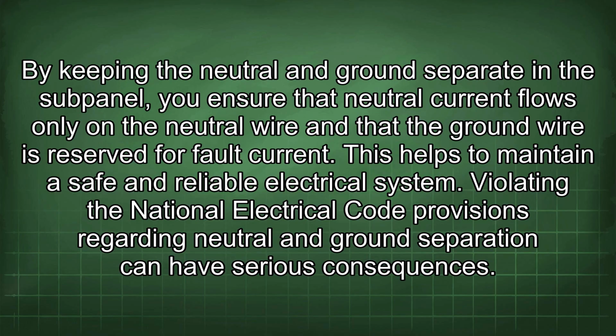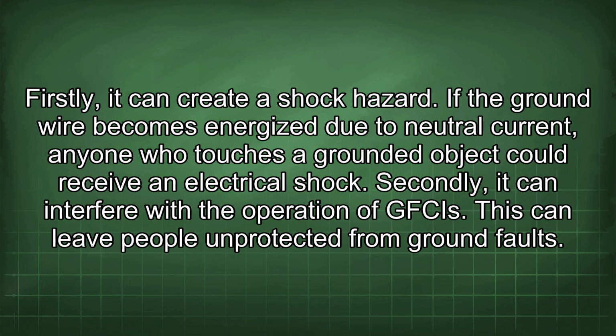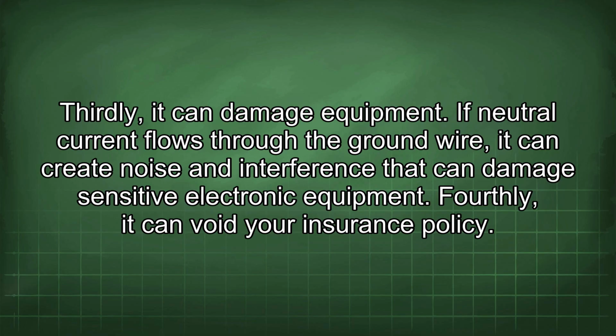Violating the National Electrical Code provisions regarding neutral and ground separation can have serious consequences. Firstly, it can create a shock hazard. If the ground wire becomes energized due to neutral current, anyone who touches a grounded object could receive an electrical shock. Secondly, it can interfere with the operation of GFCIs. This can leave people unprotected from ground faults. Thirdly, it can damage equipment. If neutral current flows through the ground wire, it can create noise and interference that can damage sensitive electronic equipment.